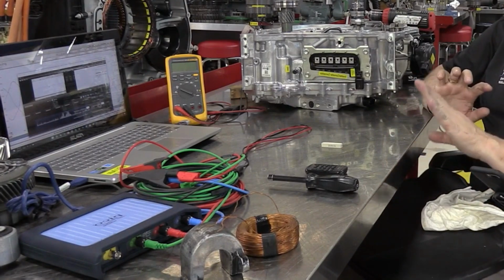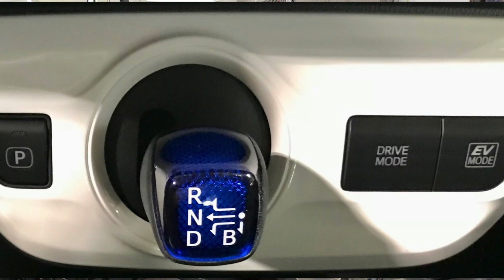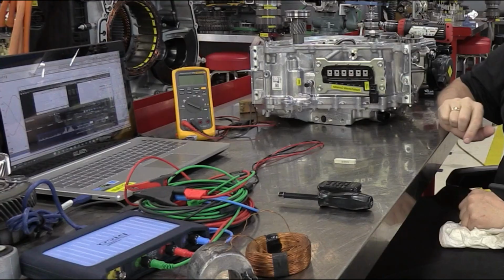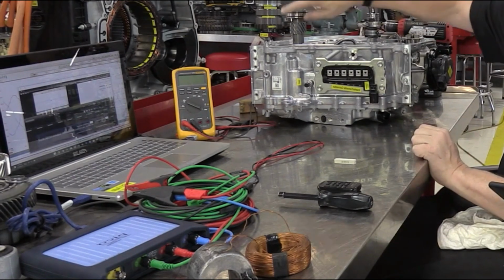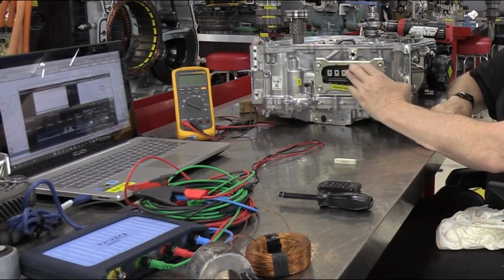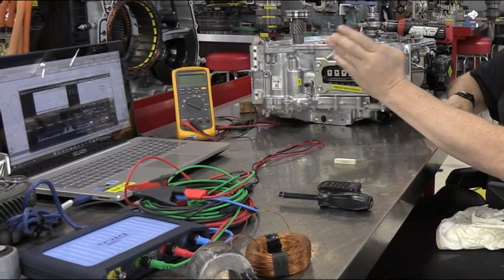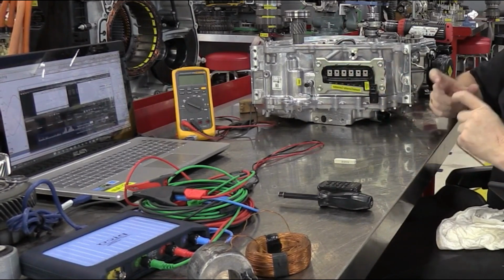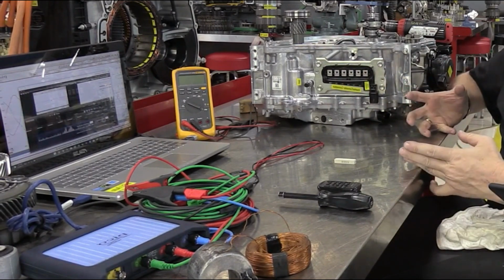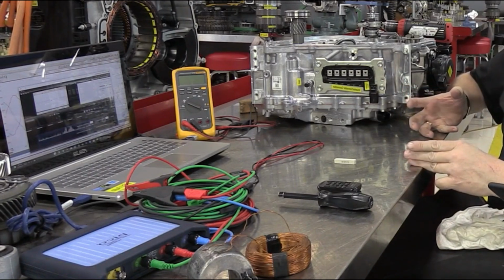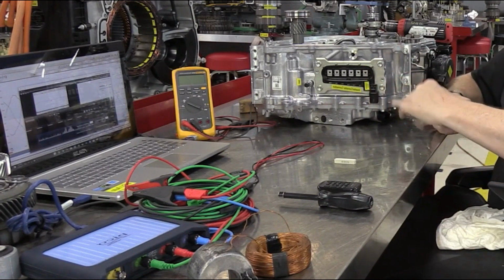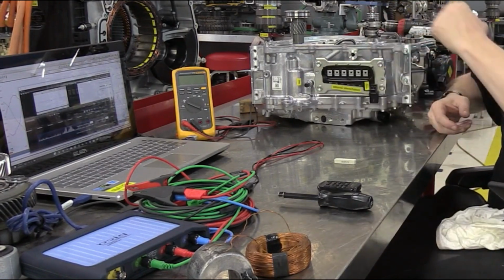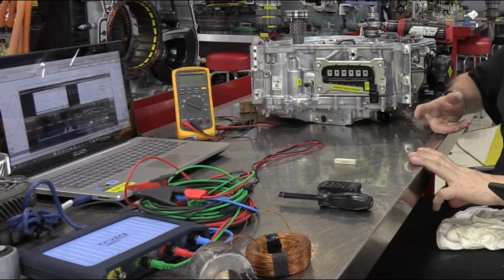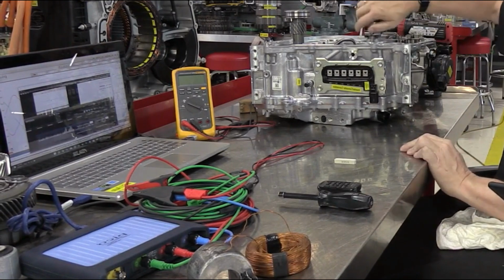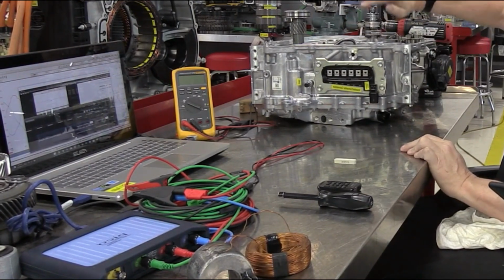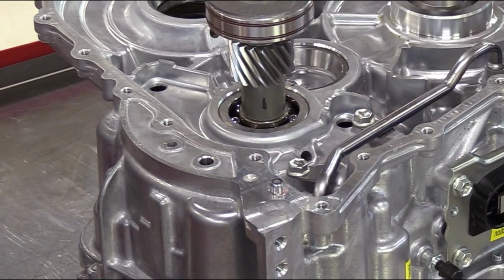Pulse width modulation is a technique used by the inverter to control the frequency and the voltage supplied to the motor. By varying the pulse width, the inverter can precisely control the effective voltage and frequency, allowing for effective motor control. Advantages: smooth speed control and acceleration, reduction of harmonic distortion, improved energy efficiency. Challenges: PWM switching can introduce electromagnetic interference and cause additional losses in the motor winding.